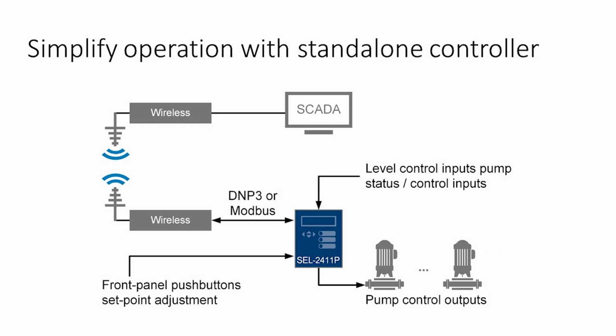What we're seeing is a lot of customers will not only replace their standalone pump controller with this product, but they'll also replace the RTU in the field. They'll get rid of their interposing relays and their phase monitor relay. All of a sudden you have a lot less components, and a single unit that's looking at everything in the station, understanding what's going on, reporting that back to SCADA, making good decisions on how that application should operate, and has expandability for future needs at that location. As we go forward, there's going to be things we want to do at these locations that we're not doing today, usually requiring SCADA interface, additional control, or at least additional data enunciation and telemetry points back to the SCADA system.